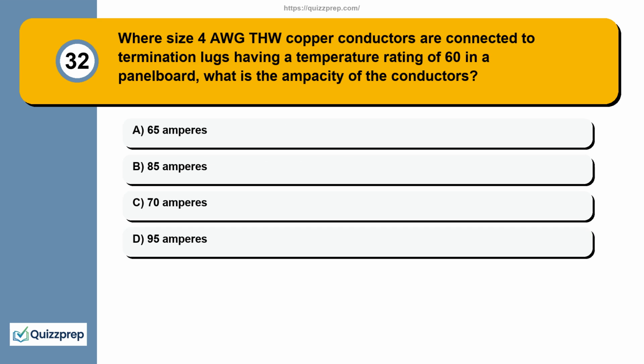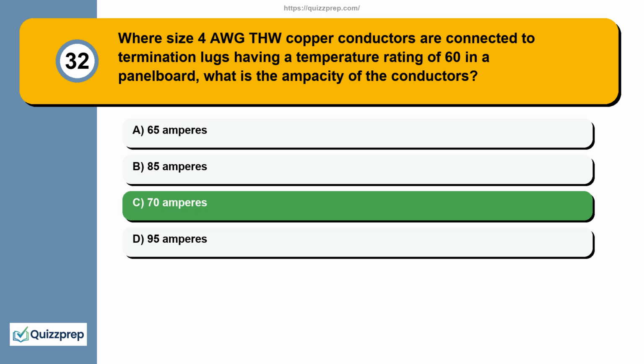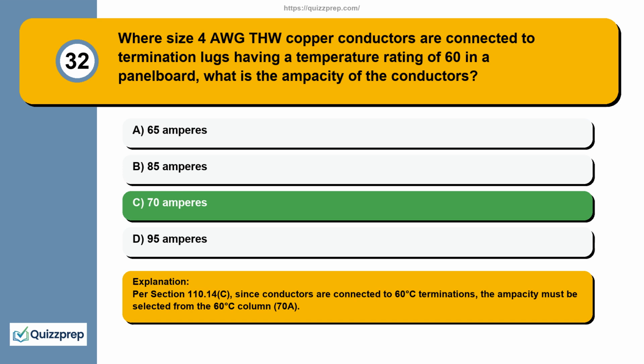Question 32. Where size 4 AWG copper conductors are connected to termination lugs having a temperature rating of 60 degrees Celsius in a panelboard, what is the ampacity of the conductors? 65 amperes, 85 amperes, 70 amperes, 95 amperes. Per Section 110.14(C), since conductors are connected to 60 degrees Celsius terminations, the ampacity must be selected from the 60 degrees Celsius column: 70 A.